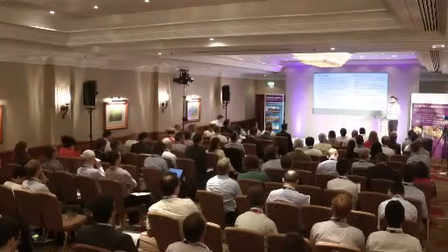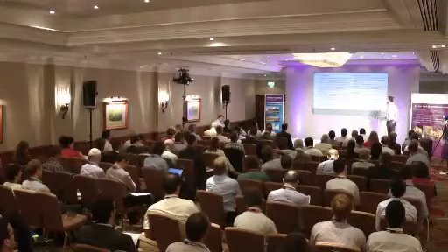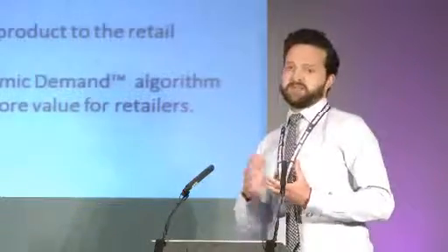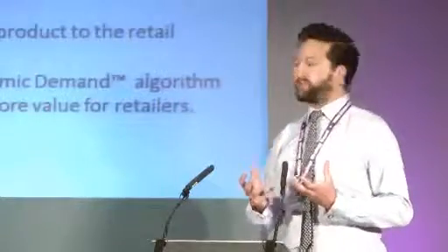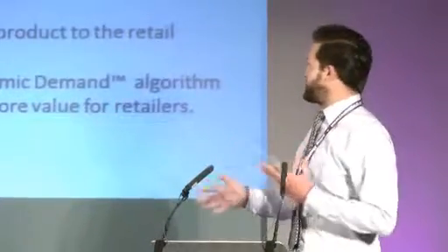The project was split into two parts. The first three months involved developing and embedding our algorithm within the Carel pack controller and testing in Carel's state-of-the-art testing lab. The second three months was trialing the system in 10 Tesco supermarkets. The trial was a market success — we hit all the KPIs and managed to harness the amount of energy we thought was going to be in each supermarket and each pack-based system without compromising any of the refrigeration alarms or the energy performance of the whole system.